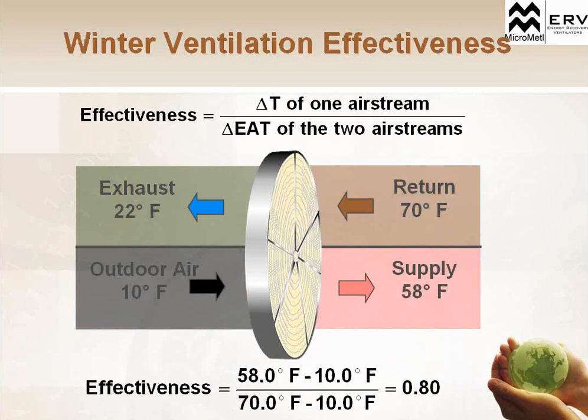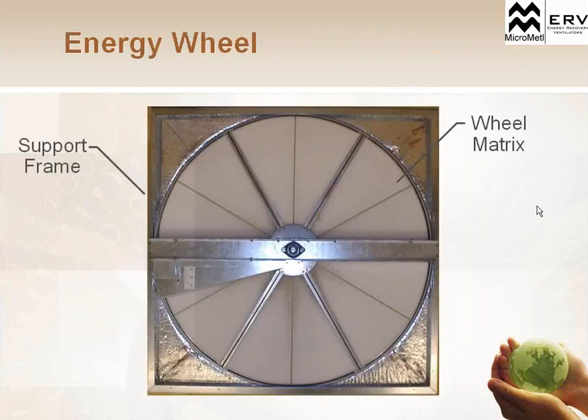If you look at the winter ventilation effectiveness, it's essentially the same equation. We're just working backwards, the 10 degrees to 58 degrees. We reverse the numbers so we don't get a negative. You get 80% effectiveness during the winter. So you'll get a summer and a winter effectiveness off of each wheel.